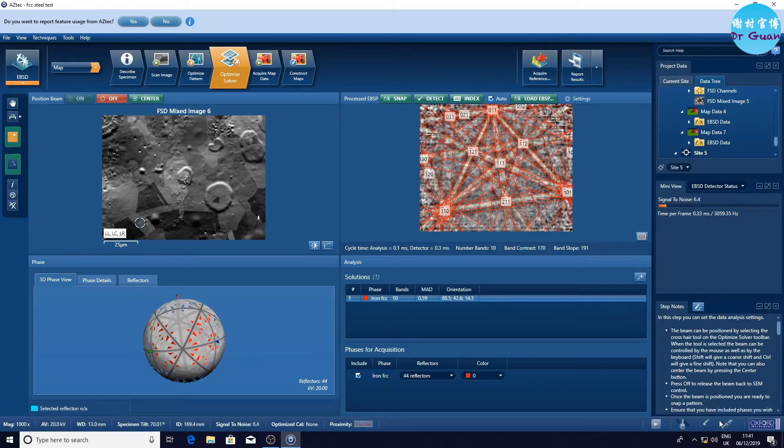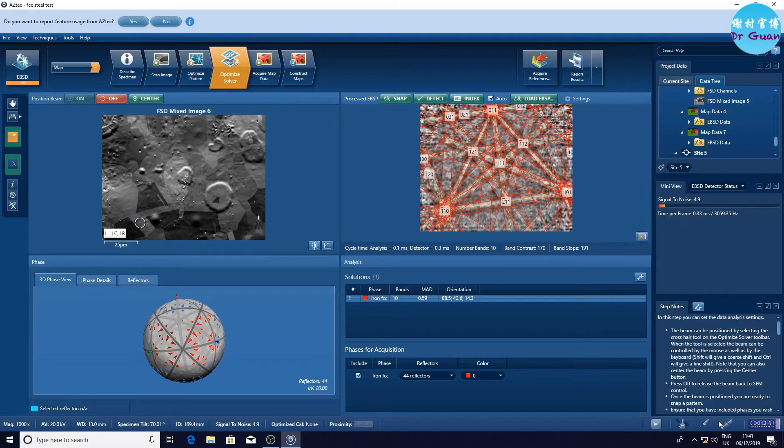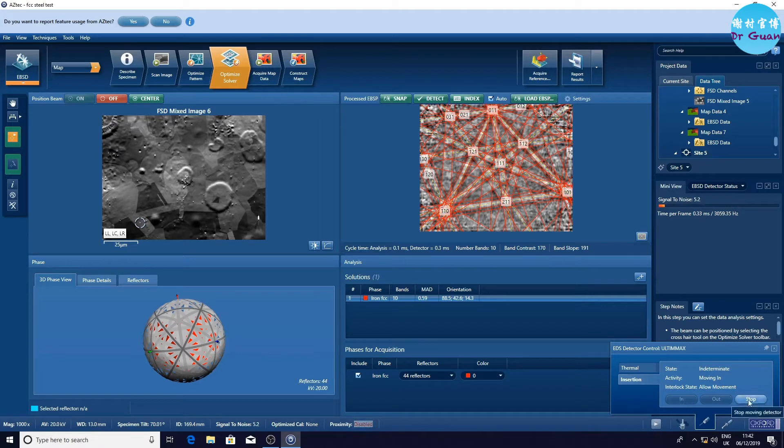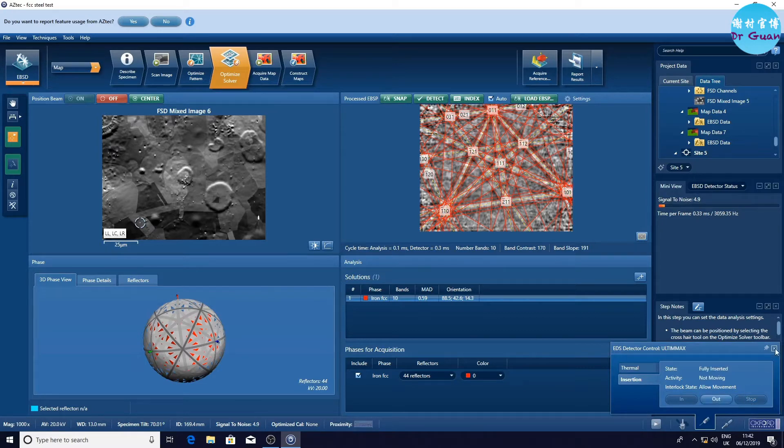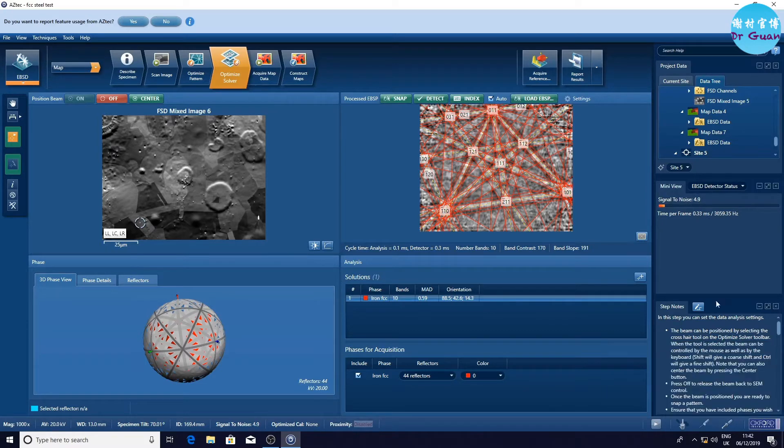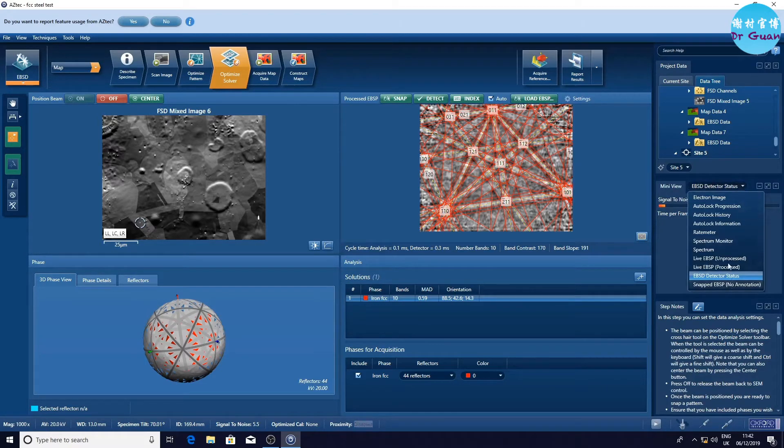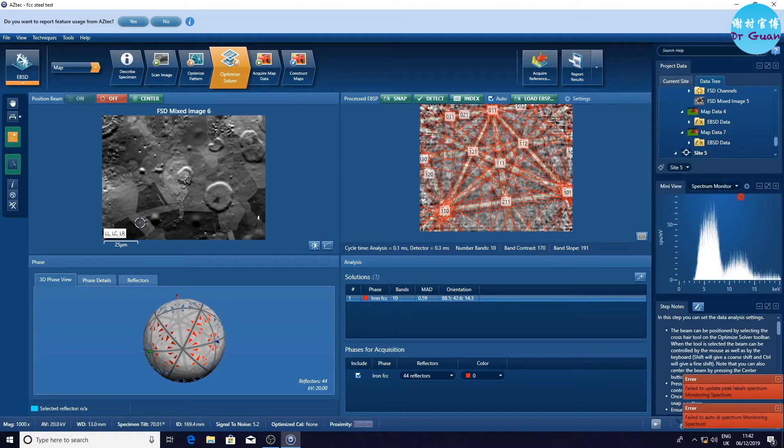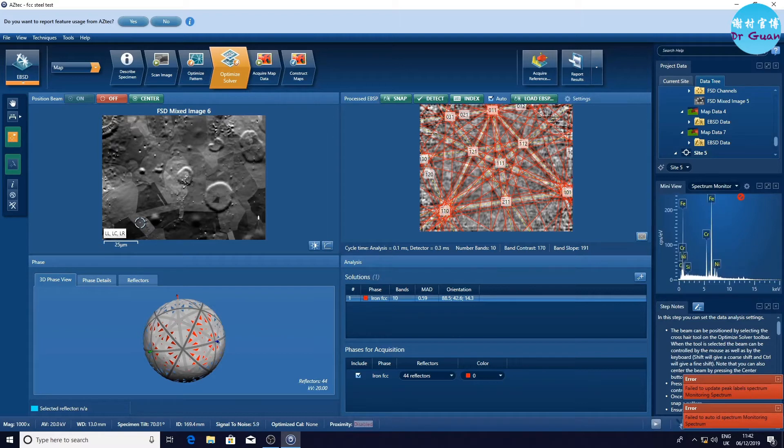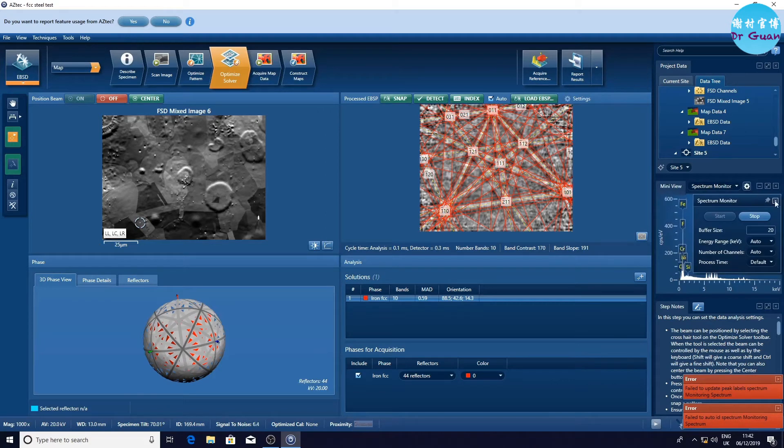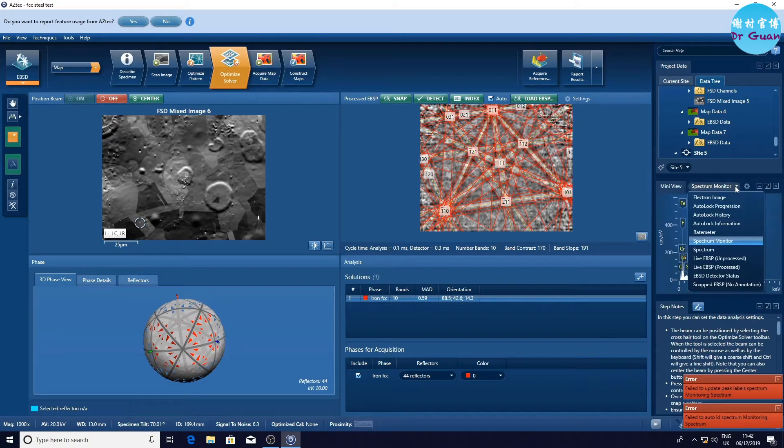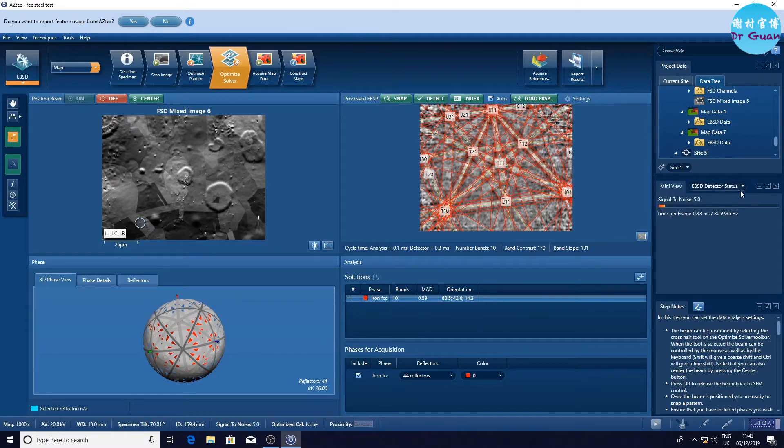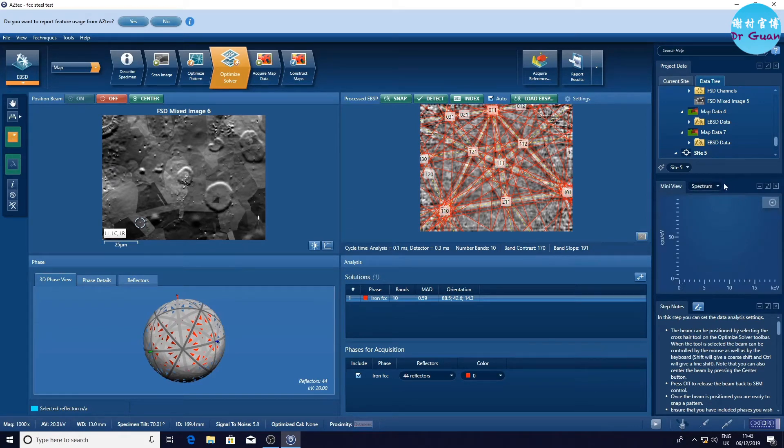The MAD is not too bad, 0.59. Now we are going to insert the EDX detector. Let's click in. Now we need to check whether we got enough signal. Now in test here, it failed to update the peak level spectrum. Maybe it's because the signal is too strong. We need to reduce the signal. So how are we going to do this? I'm not sure.